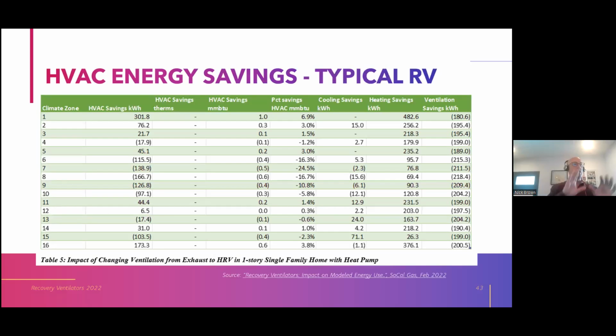And here's a chart. It's in your handout, so you can dig into it a little bit more deeply. But this was our findings for a typical RV in a 1-story home with a heat pump. You're going to get actually better savings on an MMBTU basis with a gas furnace. But I put in the heat pump table because I think that's where we're all headed, right? And you see that in the last column, the ventilation savings are negative, because of what I just showed you. We've got added fan energy for the balanced ventilation RV compared to exhaust ventilation. That's what we're comparing here.